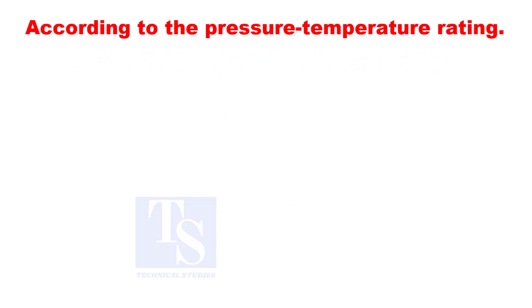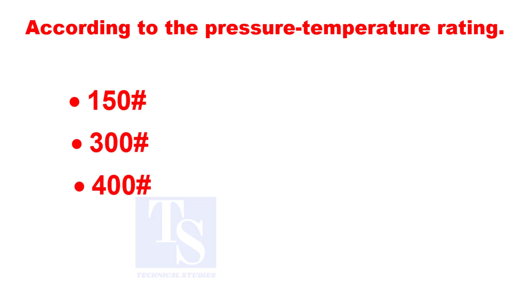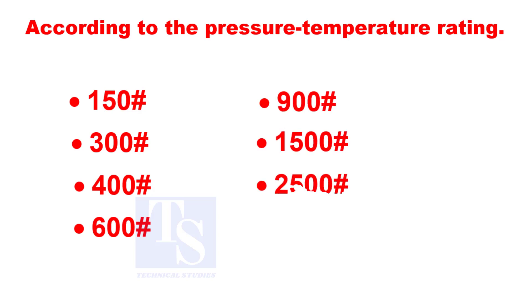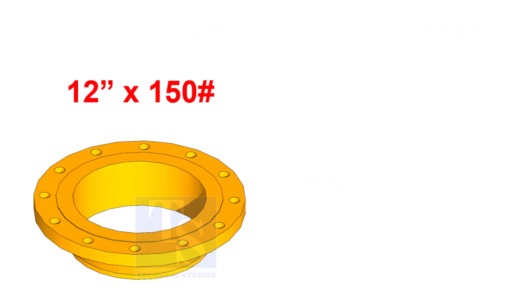Based on pressure temperature rating, flanges are of the following types: 150 lbs, 300 lbs, 400 lbs, 600 lbs, 900 lbs, 1,500 lbs, and 2,500 lbs. As the pressure rating of a flange increases, the flange dimensions, strength, and load carrying capacity also increases. Compare these flanges.